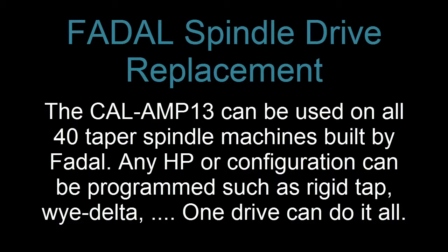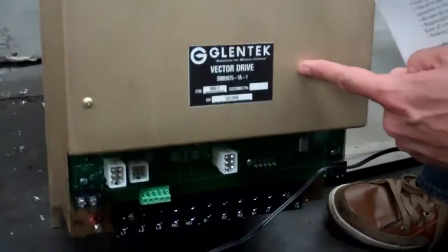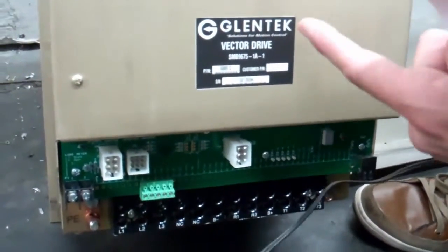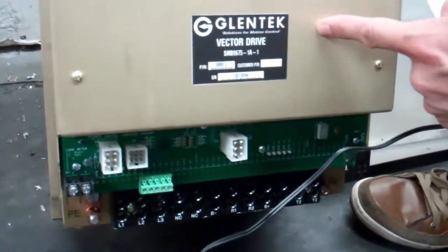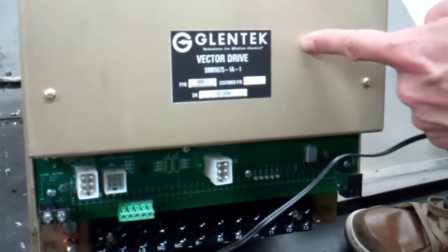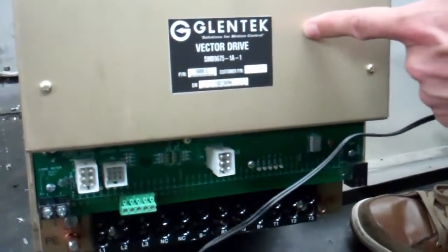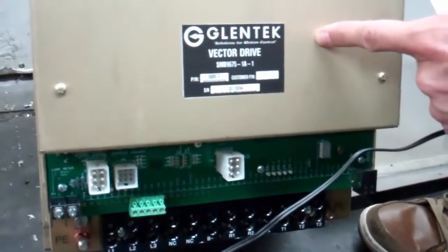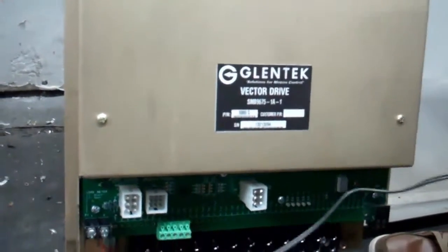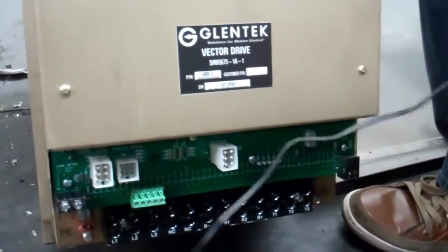What I'm going to show you today is the Glentek Vector Drive, how to set it up and install it. This is the Glentek Vector Drive. It replaces any inverter or vector drive for Fadal machines — 5 horsepower, 10 horsepower, 15 horsepower, and 20 horsepower motors. Whether the motor has an encoder or does not have an encoder, it will also do rigid tapping. So this will handle any inverter or vector drive replacement you need to get done.